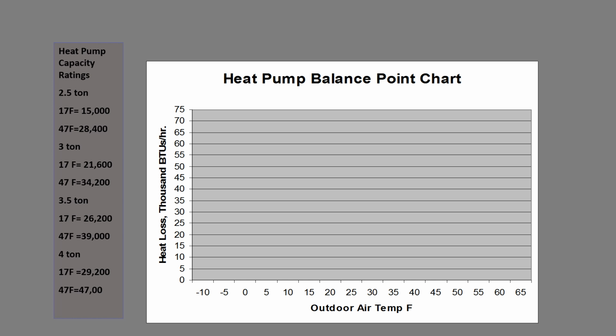So this is sort of an old school heat pump balance chart. The first thing that you do is that you do the heat loss calculation for the house, and you draw a line down to 65 degrees. And sure enough, the warmer it is outside, the less BTUs we have to pump into the house to maintain comfort.